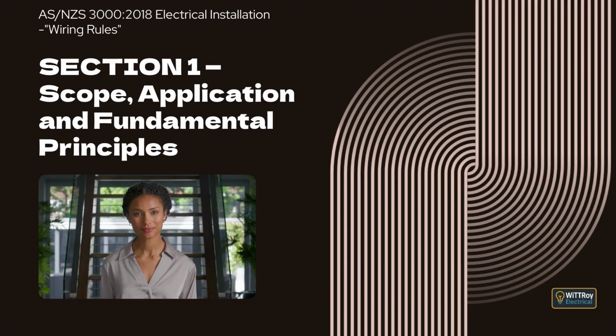Clause 1.4.43 is current, short circuit. This is a fault current that results from a fault of very low impedance between live conductors under normal operating conditions. The fault path may include the path from the active to the neutral conductor. This is also known as the prospective short circuit current or the bolted fault. Unless stated otherwise, this value is the three-phase RMS value at the relevant point in the installation.